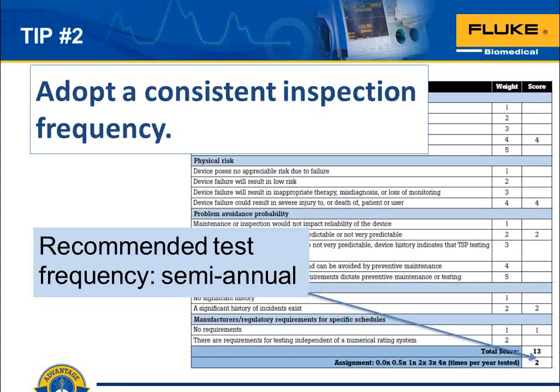Tip number 2, adopt a consistent inspection frequency. So whether you're following the manufacturer's inspection frequency or an adjusted inspection frequency that you've come up with using, for example, this risk-based methodology that I'll talk to you about in a minute, you should come up with this frequency of inspection and then stick to it. And then any changes that you need to make to it, you need to make sure you're providing a rationale, a reason why you're making the change, what changes you're going to make, and how you validated those changes to make sure that you know that they're going to deliver the expected results. And that means keeping the medical device, the ESU in this case, safe and effective for clinical use.